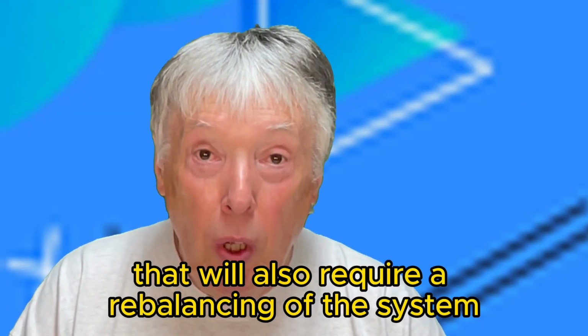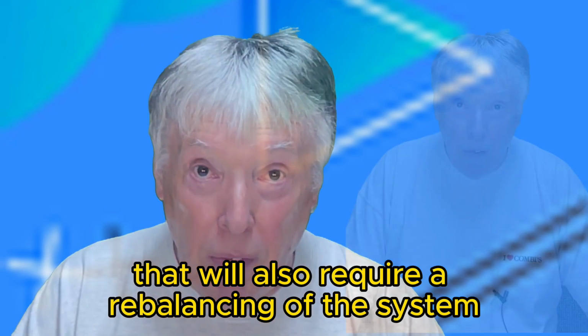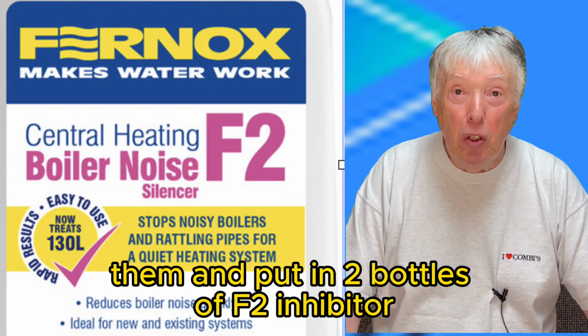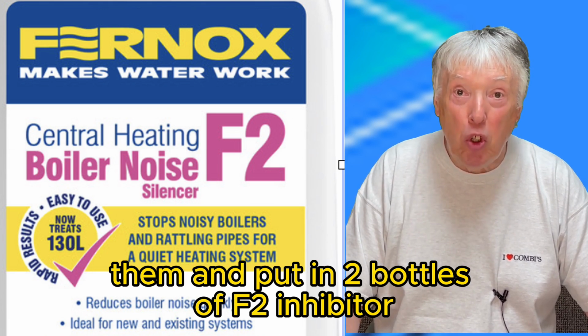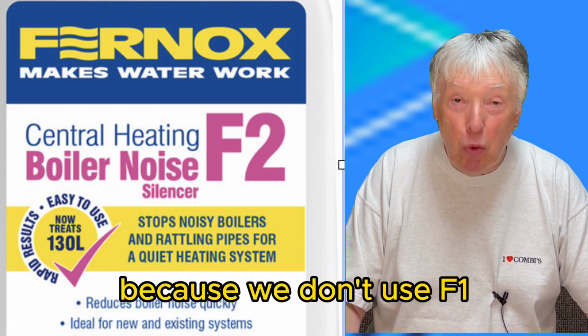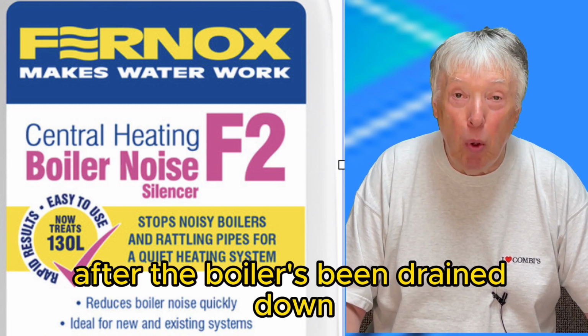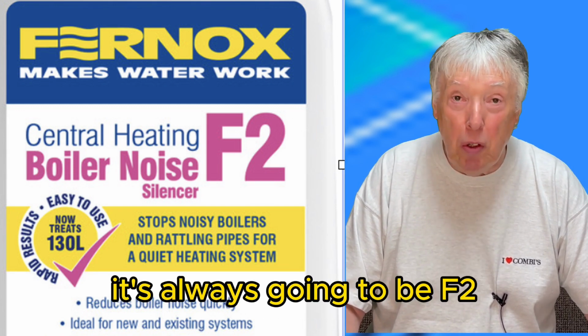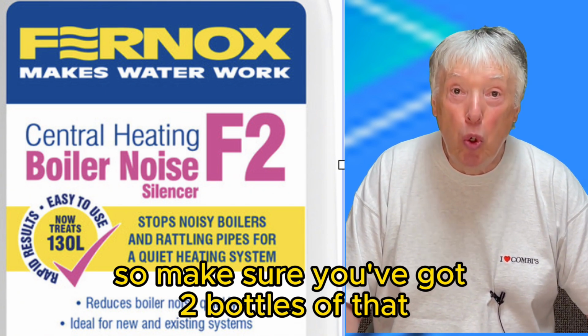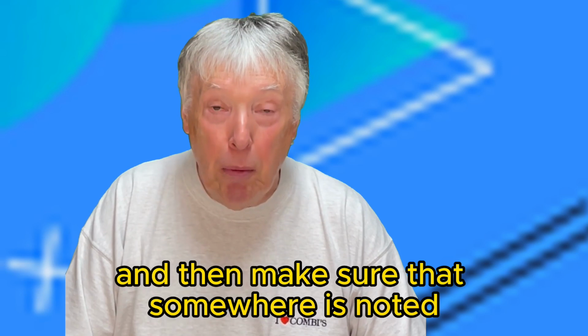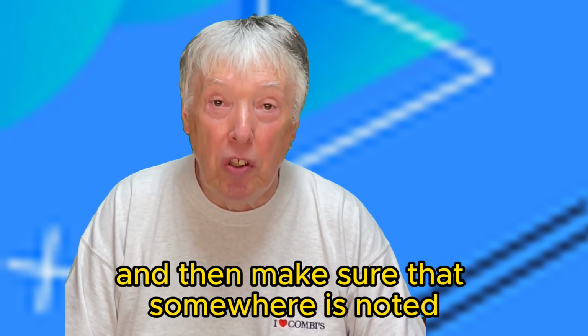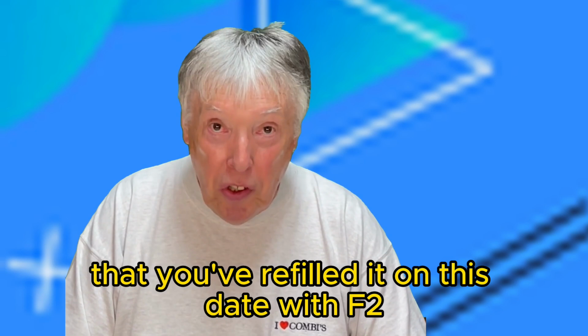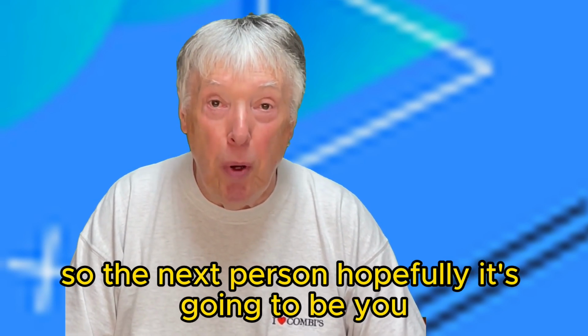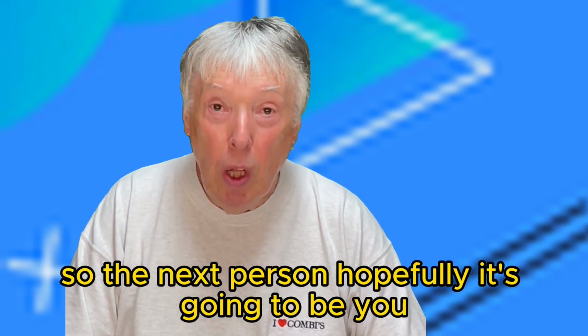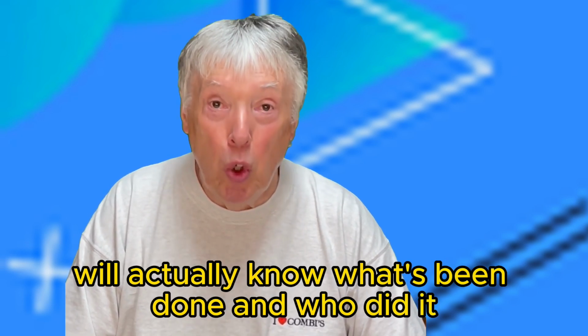That will also require a rebalancing of the system and putting in 2 bottles of F2 inhibitor, because we don't use F1 after the boiler's been drained down. It's always going to be F2, so make sure you've got 2 bottles of that. So flush the system out, follow the instructions, and then make sure that somewhere is noted that you've refilled it on this date with F2. So the next person, hopefully it's going to be you, will actually know what's been done and who did it.